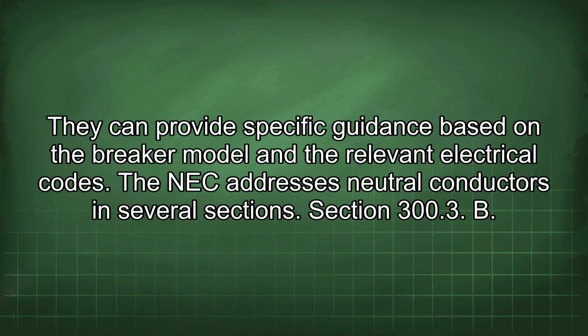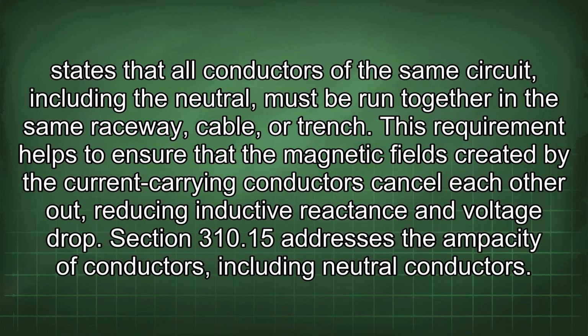The NEC addresses neutral conductors in several sections. Section 300.3(B) states that all conductors of the same circuit, including the neutral, must be run together in the same raceway, cable, or trench. This requirement helps to ensure that the magnetic fields created by the current-carrying conductors cancel each other out, reducing inductive reactance and voltage drop. Section 310.15 addresses the ampacity of conductors, including neutral conductors.